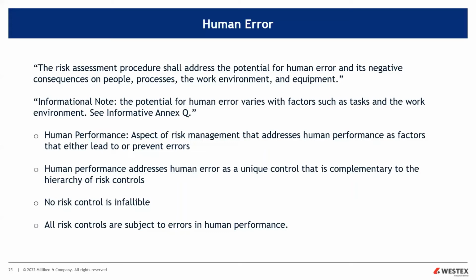Now, of course, human error also affects the risk assessment method used, and when to revisit the risk assessment. Complacency is a safety killer and can occur in the assessment procedure or the reassessment procedure, if you will. The erroneous thinking can be, hey, our facility's electrical system really hasn't changed much, right? It's a minimal change, so we don't really need to revisit the assessment, right? Wow, really? How long has it been since the facility's assessment has been looked at? Has the electrical utility that supplies your organization notified your company about changes in the utility's actual available fault current to your facility? Has the utility changed the parameters on the final utility overcurrent protection device?